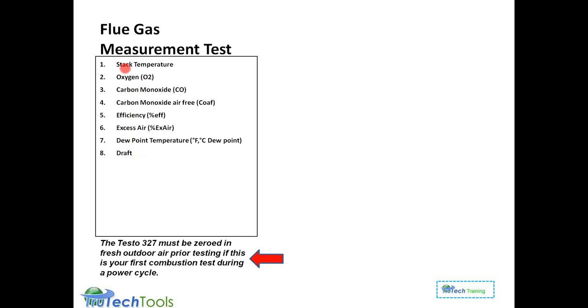If you really wanted to get crazy, you could put CO in all lines on the display. It won't come out on the printer because the Germans are conservative and they won't waste paper, but it will come up on the screen as many times as you enter a parameter on the screen. So dew point temperature, that's a calculation based upon the fuel that you're burning. And draft is another parameter that can be measured, that can be shown on the screen.